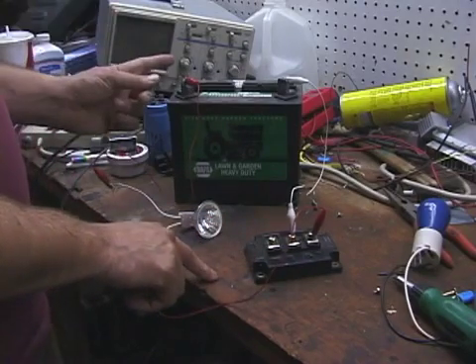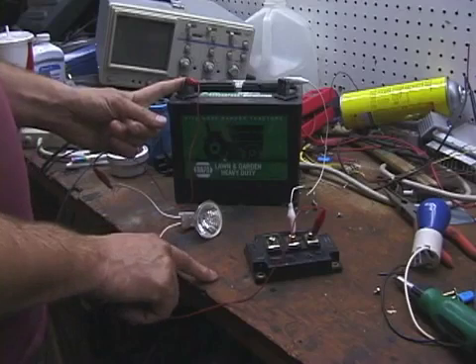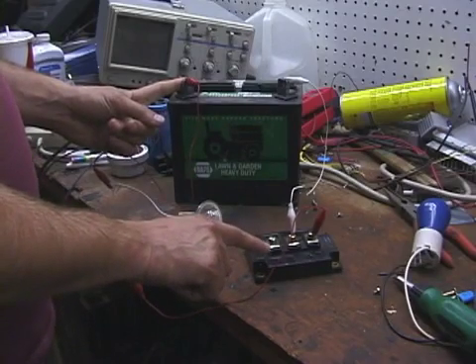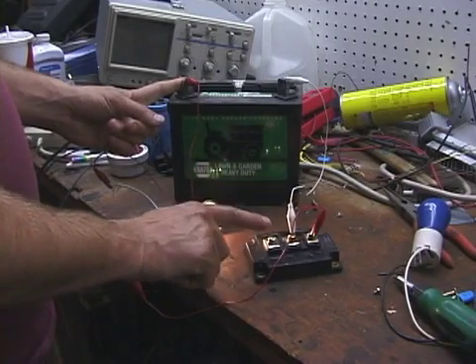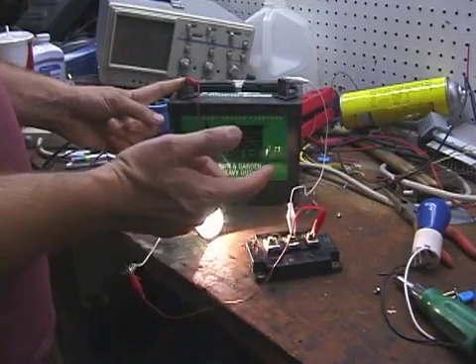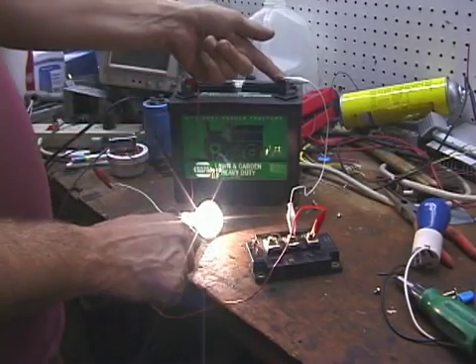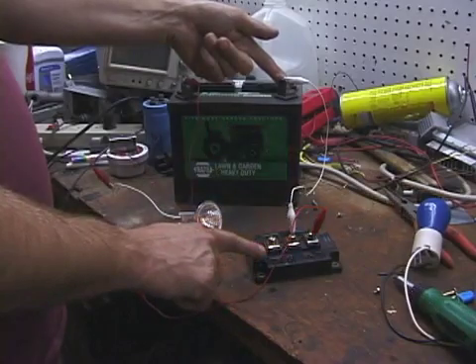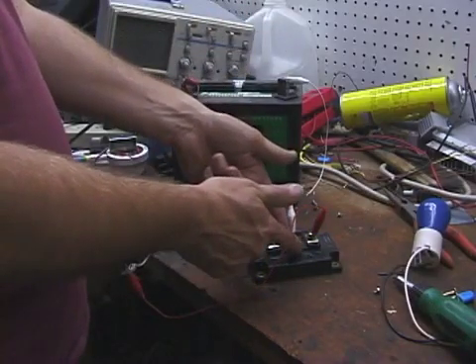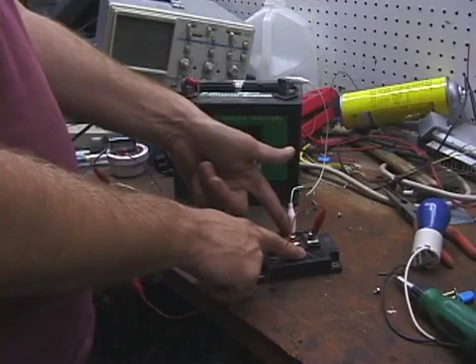So what we'll do is touch the positive battery terminal, and then I'll touch the spade connector for G2. And as you can see, the light turns on. If I touch negative, the light goes off. So we know the second IGBT in this brick here is okay.